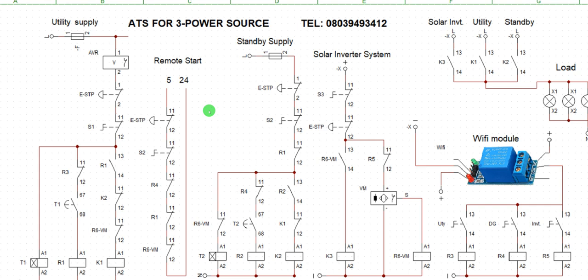Once the simulation passes testing, you then purchase the components and carry out the wiring. Contact me and we'll design this together — it's a very simple design. ATS can synchronize up to 10 or more power sources, alternating them as needed. You can set one as prime and one as standby, or even design the ATS to alternate sources between day and night operation, depending on your design method.